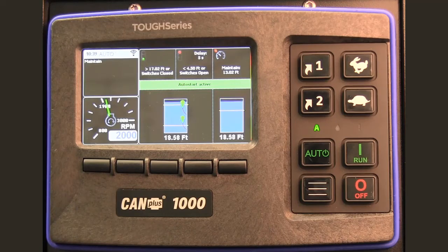Now when the level starts to drop and reaches 13 feet, the CP1000 will adjust the throttle appropriately to maintain the specified level. If the level gets below the maintain point, the throttle will be adjusted to reduce the RPMs to the actual required run speed to maintain the point at 13 feet.